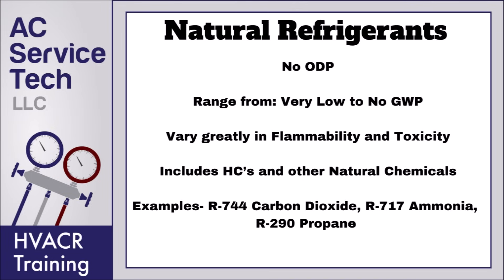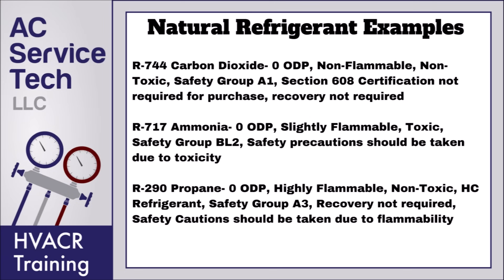Natural refrigerants have no ODP and range from very low to no global warming potential, and they vary greatly in flammability and toxicity. This category includes HC refrigerants as well as other natural chemicals. R744 is carbon dioxide: zero ODP, non-flammable, non-toxic, safety group A1, and section 608 certification is not needed to purchase R744. R717 is ammonia: zero ODP, slightly flammable, toxic, safety group B2L, and safety precautions should be taken due to toxicity. R290 is propane: zero ODP, highly flammable, non-toxic, HC refrigerant, safety group A3, and recovery is not required, though safety caution should be taken due to flammability.